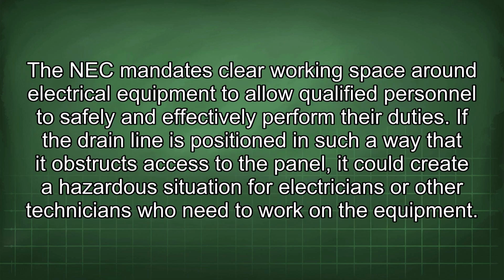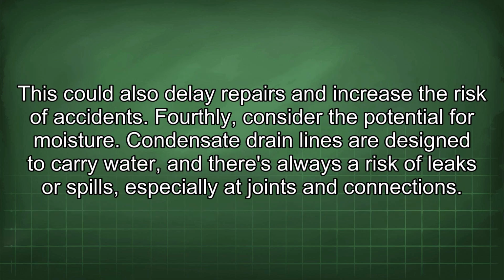The NEC mandates clear working space around electrical equipment to allow qualified personnel to safely and effectively perform their duties. If the drain line is positioned in such a way that it obstructs access to the panel, it could create a hazardous situation for electricians or other technicians who need to work on the equipment. This could also delay repairs and increase the risk of accidents. Fourthly, consider the potential for moisture.